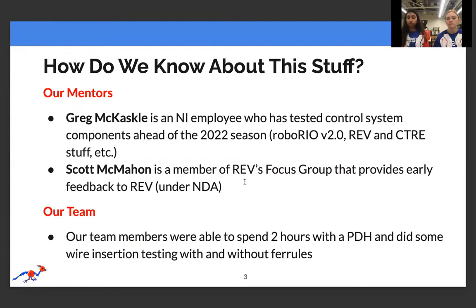Our team members spent 2 hours with the PDH and did wire insertion testing with and without ferrules. We found that our 4-gauge wire with our 4-gauge ferrule was not fitting tightly into the port, and the 6-gauge ferrule was not fitting onto the 4-gauge wire. So we will be bare wiring our 4-gauge wire.